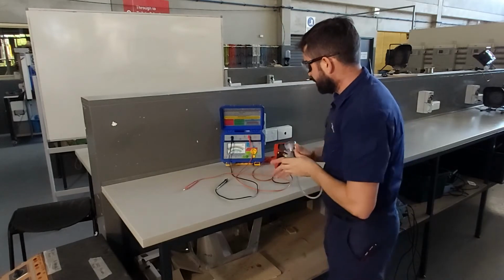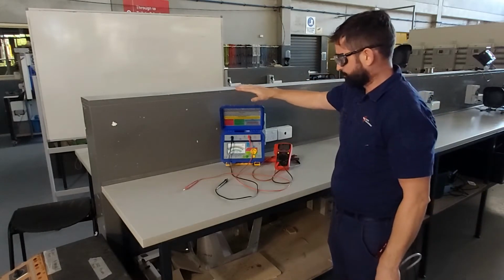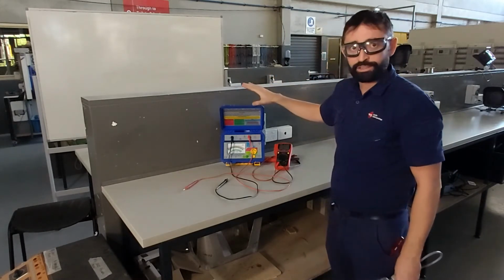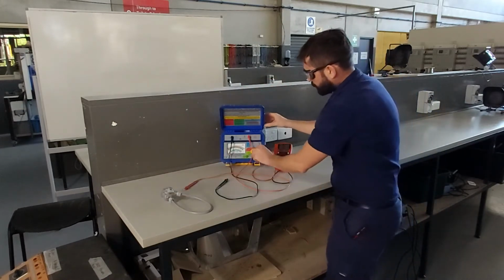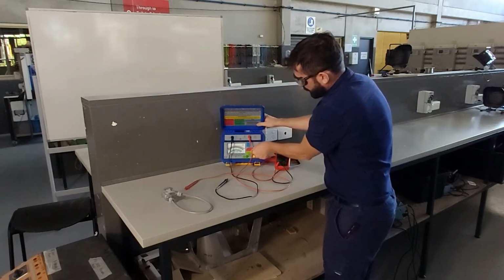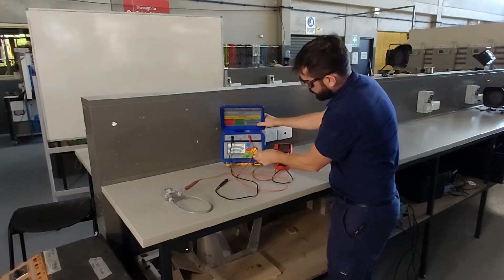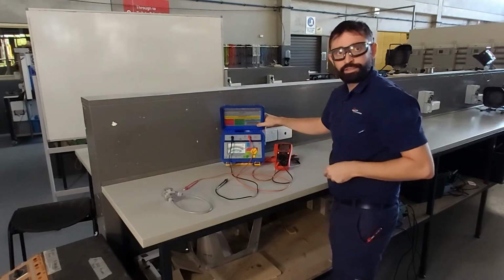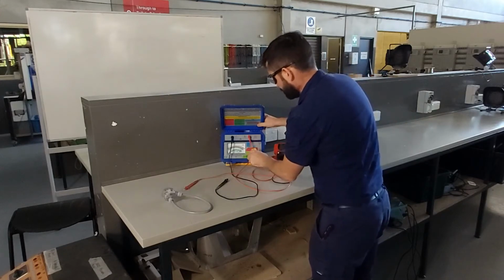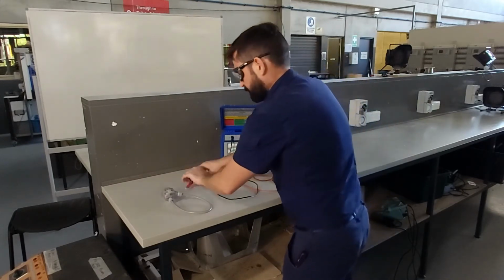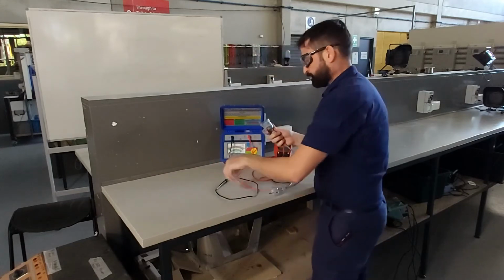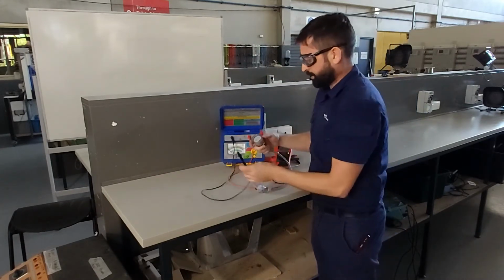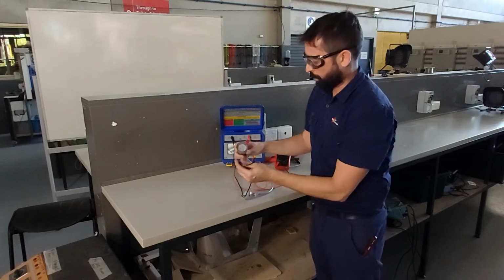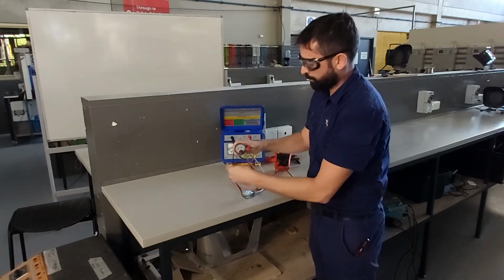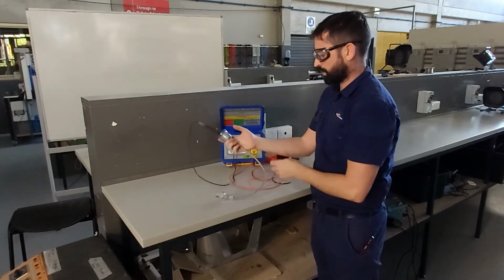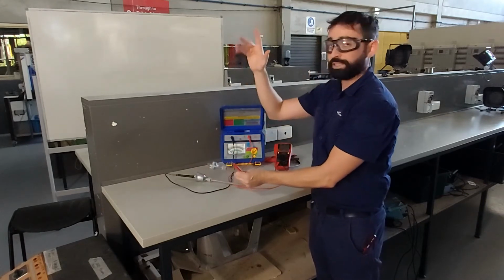So how we do that is using our insulation resistance tester. Now I already did a calibration check on this earlier, but this also has a battery check. Now I'm going to turn the dial down to battery check. Lock it in place. Now, battery's okay. That tells me the battery's fine to use. Next, we are going to stick one of the probes in. Remember, we test everything down to earth with insulation resistance. So one of the probes is going to go in the earth terminal, like so. Right, and we can leave that like that. Okay, our other hand's free.